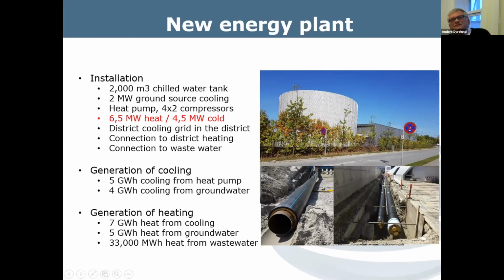The total capacity of the cooling network is 10 megawatts, but combined with the storage tank and ground source cooling in the next stage, we'll be able to supply all this capacity, saving a lot of individual chillers in the buildings. The cooling energy itself is not that big, only 10 gigawatt hours, a combination of process cooling and comfort cooling.